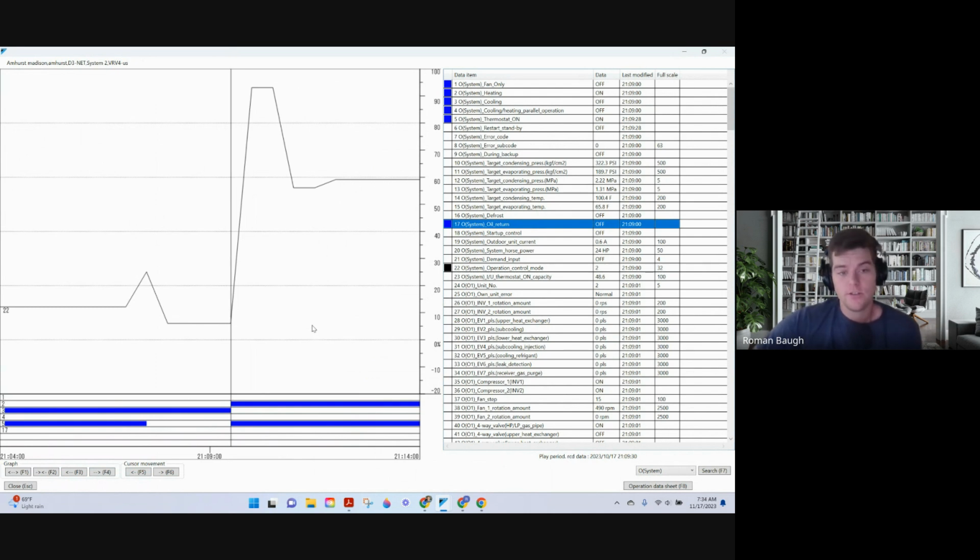And instead of chasing your tail for a couple hours, trying to figure out why is the pressure getting so low? Maybe it's low on charge. Maybe there's a restriction. No, it's normal operation. Go to the next data set. Go where you find irregular issues.